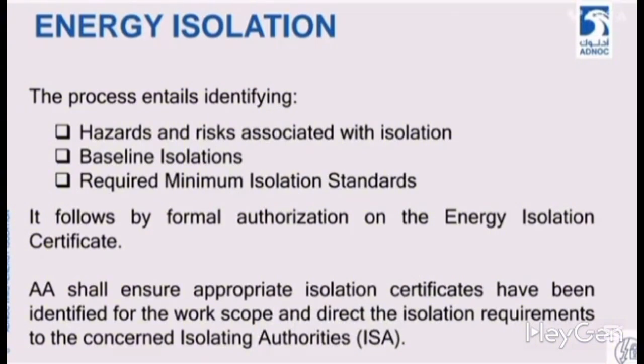Secondly, baseline isolation. Do we require a baseline for isolation, or do we need minimum isolation standards? You need to completely shut off the source of ignition or the source of your energy, or can you temporarily block it to proceed with your work? For this, there should be a relevant Energy Isolation ICC, Isolation Confirmation Certificate. Operations and energy isolations require a certificate.